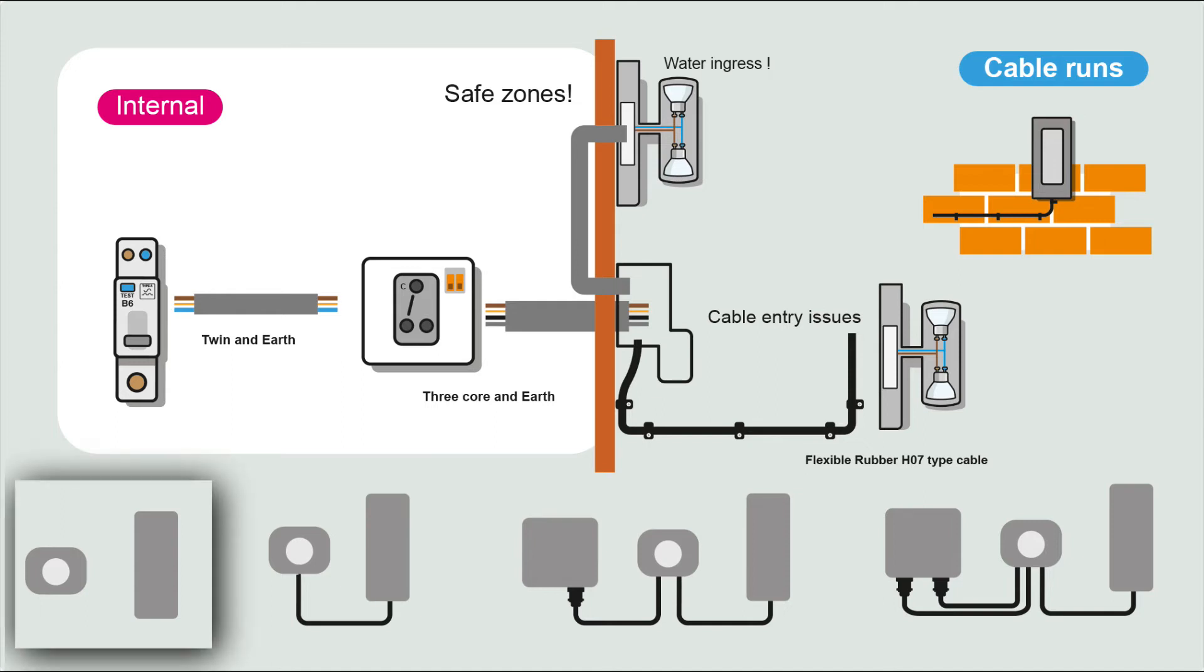It's nice if you've just got the PIR and you've got the light fitting. If you don't see any cable, that's the neatest and cleanest way of doing it. Or you might have to run some flex between the two, or you might have a junction going onto the PIR and onto the light. And again, you've got more cable. And if you've only got three-core and earth cable, then you've got more cable. If you do have to surface mount cable and you're feeding a PIR, you want to get some four-core flex. So you'll have your switch live, permanent live, neutral, and CPC. And you won't have this situation here - two cables go onto the PIR, you've got your live, your neutral, your CPC, and one cable, but you need the switch live as well. Often in that situation, people are tempted to use the CPC as one of the live cores. Can't do that. Don't use the CPC as a live core.